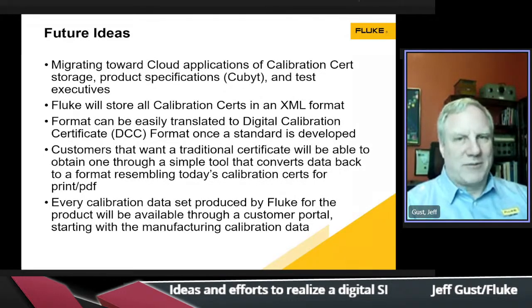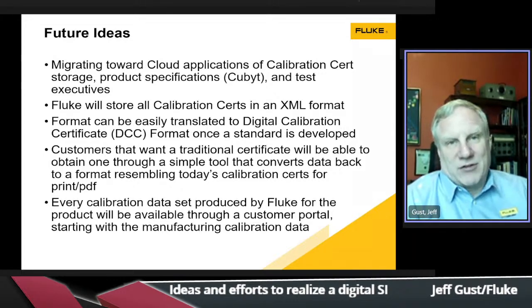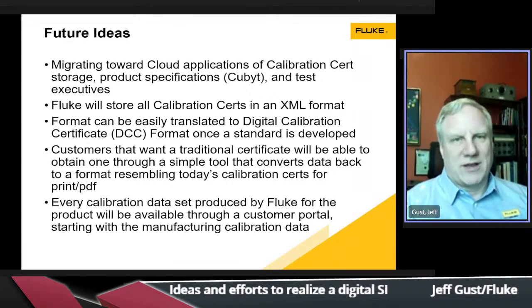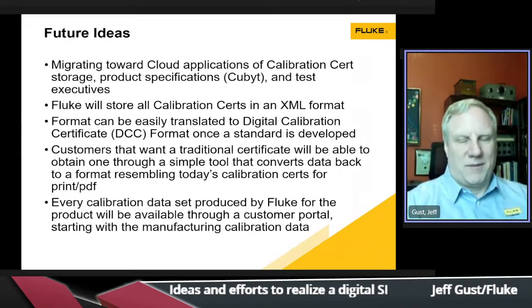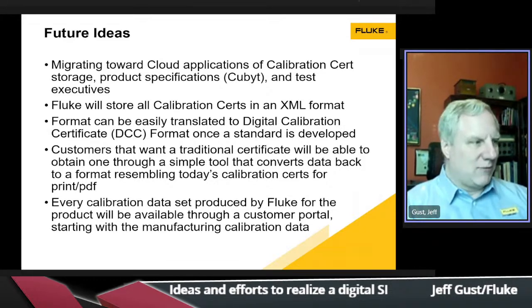We want that because when you're performing calibrations, the first thing you need to understand is the product specifications. What are we trying to test for a product, and what is its expected performance? So it always starts with the product specifications. We're also doing some work, and we're not there yet, we're still a few years out, on cloud-based test executives where you could connect to the cloud, to your device under test, and perform the calibration. The end goal is that we can do calibrations in situ at the customer's location, maybe deliver the reference standards to the customer, connected up to a cloud-based application, and then perform the calibration. That is a goal or a dream of what we're looking at doing.